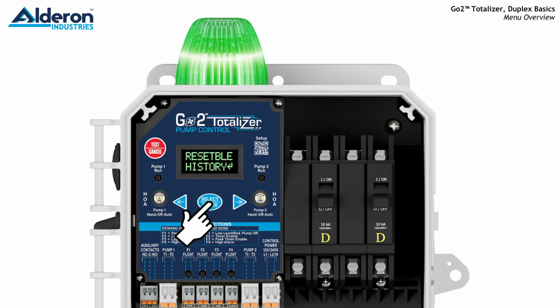Under Resettable History, the monitored data can be reset to 0, while lifetime history is non-resettable. Let's view Pump 1 stats. You can view the run stats, which include last pump duration, elapsed time in hours and minutes, average run time over last 10 cycles, minimum run time over last 10 cycles, total gallons pumped. You must enter the gallons per minute under Settings to activate. Also shown are last pump run amps, average, minimum, and maximum pump amps over last 10 cycles, and pump counts.